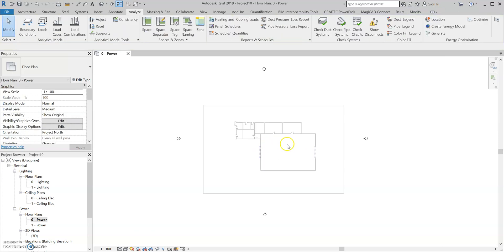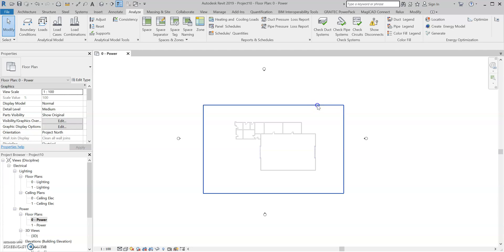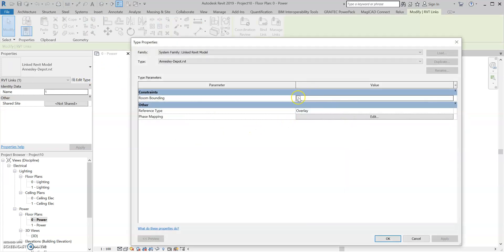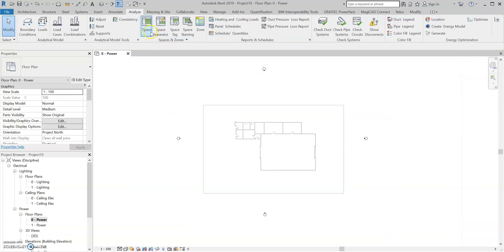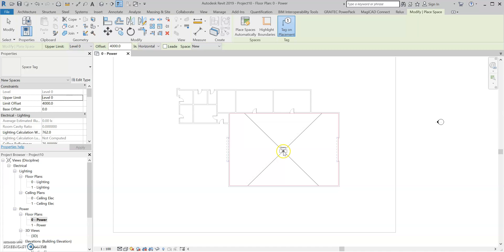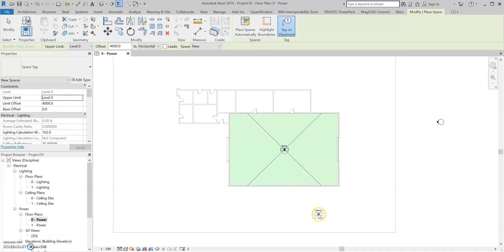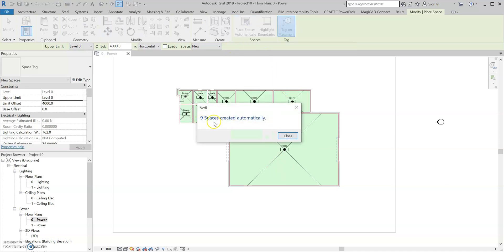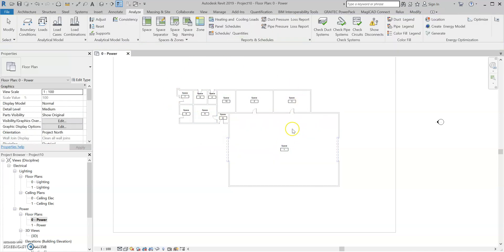To get this to work properly, we're going to select the link, edit the type, and tick Room Bounding. Select OK. So now when you put in a space, it goes to the perimeter of the room. You can either do this manually, or you can press Place Spaces Automatically — nine spaces created automatically — and we can now see them here.